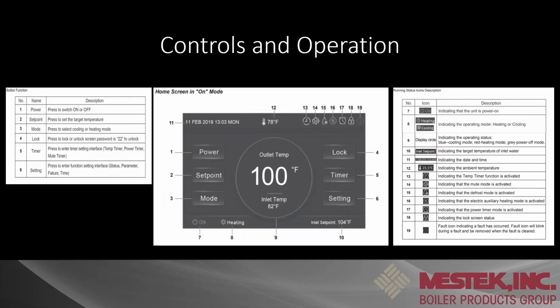The control, just to give you an idea of what the touchscreen looks like. If we look at number 1, that's press the switch on and off, right? So power, we're going to hit it and power it up. 2 is your set point. So if we want to change our set points on this product, whether you're going to go 140 or you want to go 120 or 100 or even lower, same on the cooling side, deciding on what you want for delivered temp, that can be adjusted.